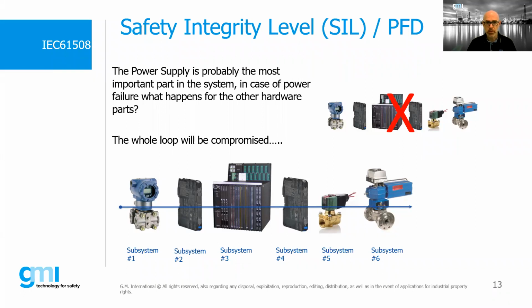All the power supplies that will be part of the SIS, for example, those that will power the PLC and DCS, those that will supply voltage to operate valves and actuators, those that will allow barriers, isolators, and transmitters to work properly, will also play a fundamental role in a safety-related loop. And it's also important that they also have an adequate SIL level. All components of a SIS, including power supplies, must be safety related and have a SIL level.